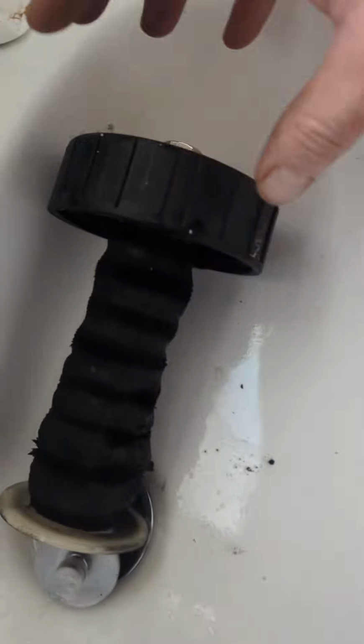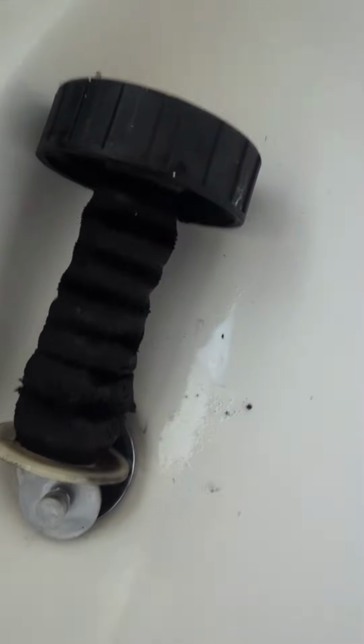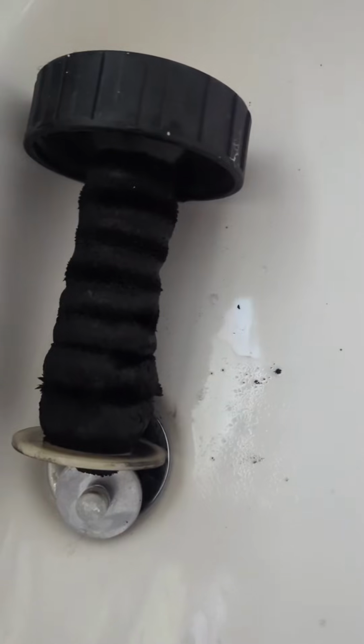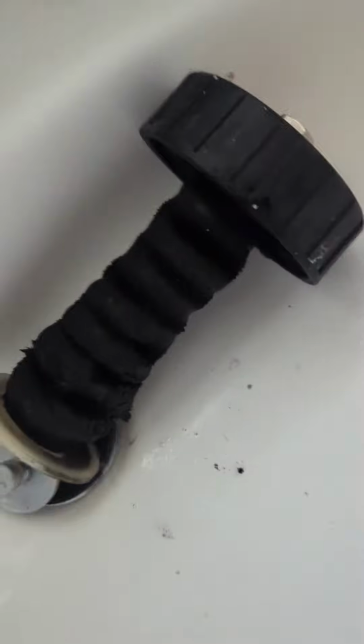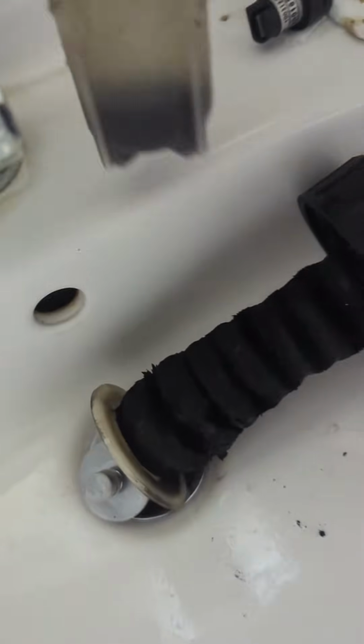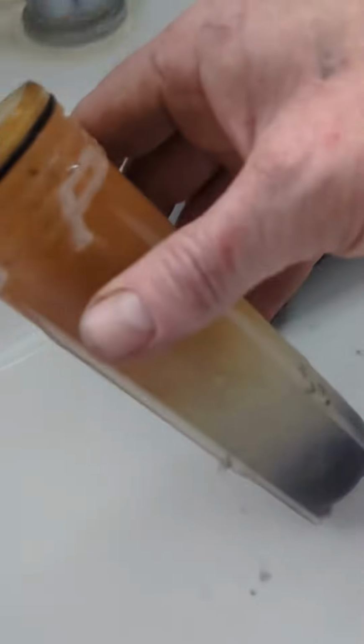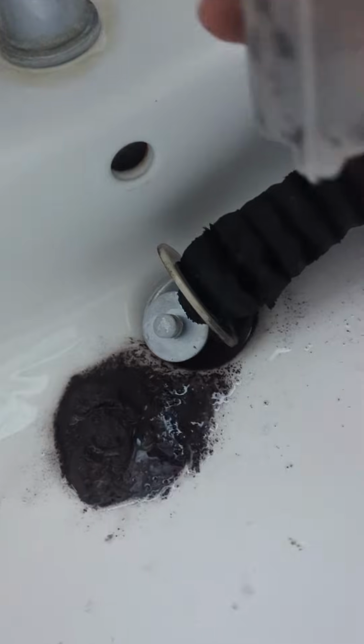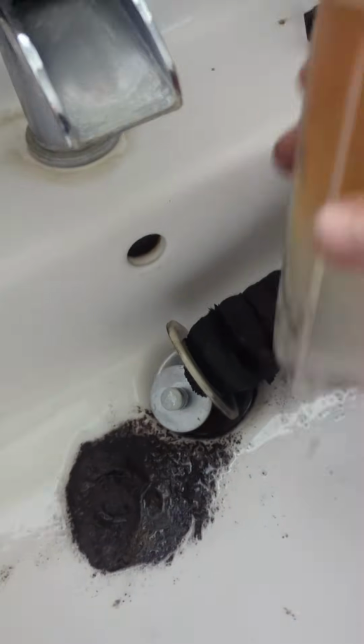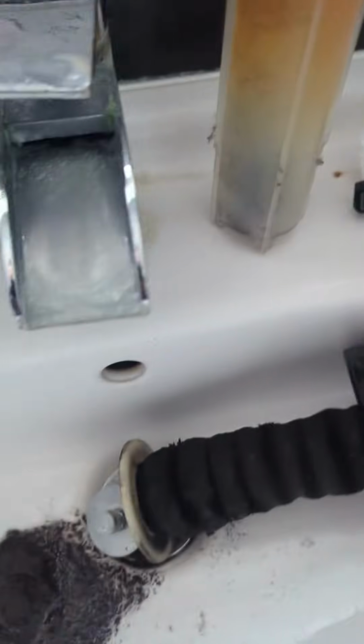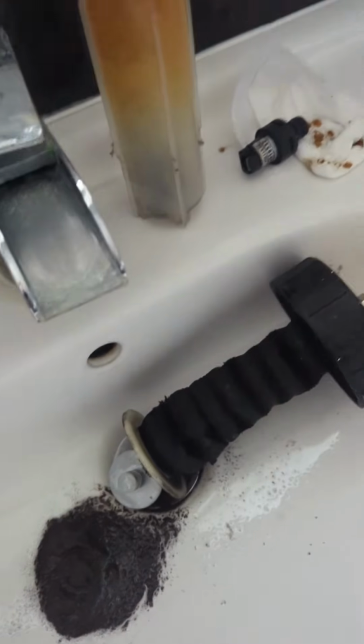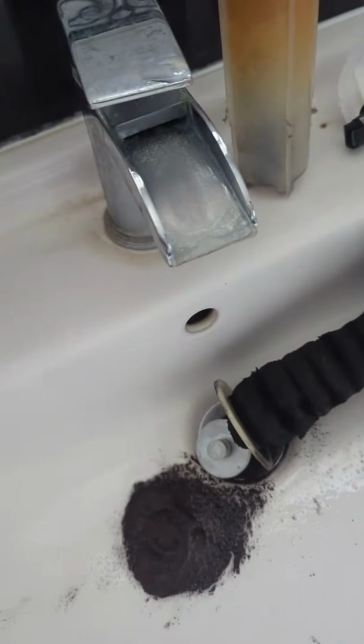This is the magnetic filter. It's absolutely stinking. We wouldn't expect this much dirt on it, but it looks like it hasn't been cleaned for years, or we've got a very dirty system. And this is the condensate trap, and we have a look. It's a hell of a lot of muck. That's a lot more than you'd expect after a year. Now, it's the first time I've been to this boiler, so it either hasn't been serviced for a long time, or it hasn't been serviced properly.